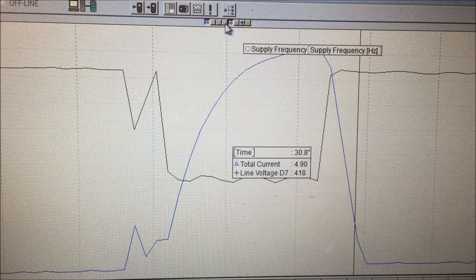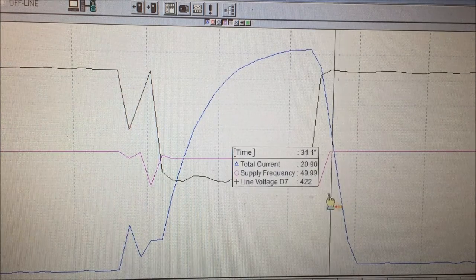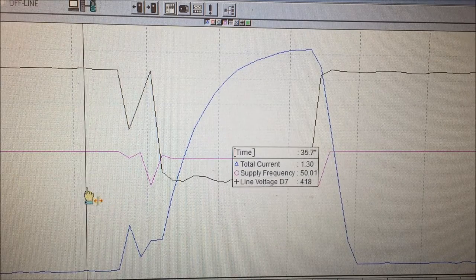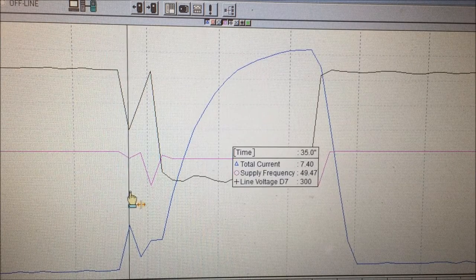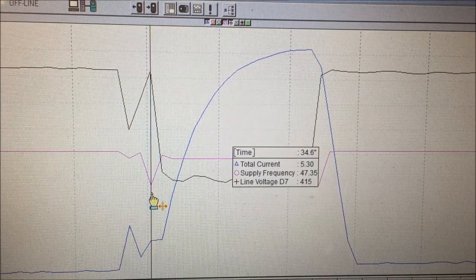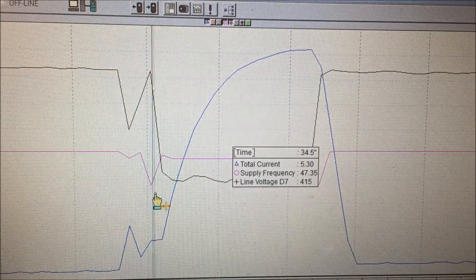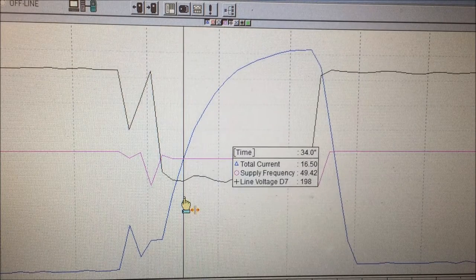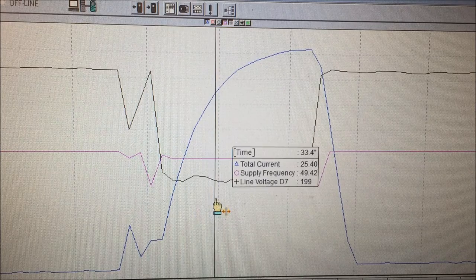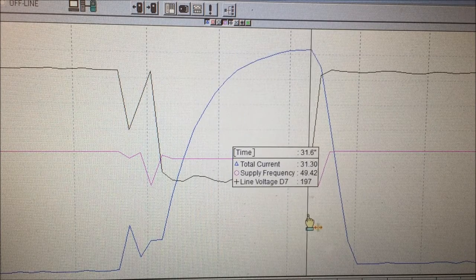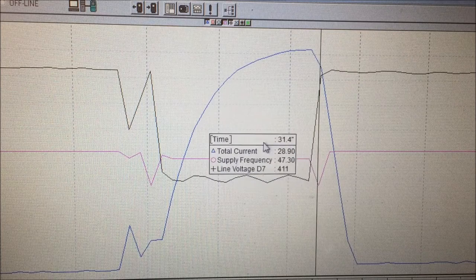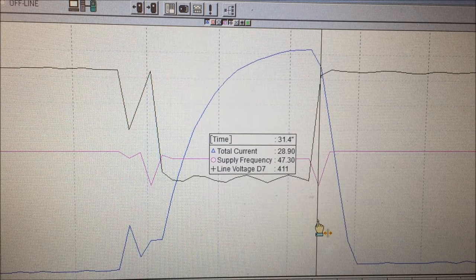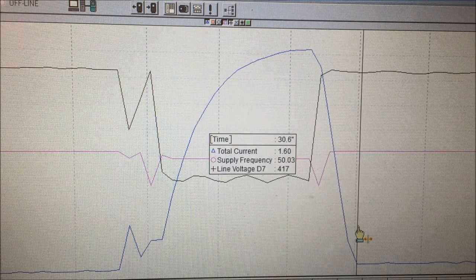What happened with the frequency when this happened? Here we can see the frequency is 50.01 and it doesn't drop here. The moment before the current cutter establishes it comes back into 49.42 hertz, keeps the frequency up during the current cutter operation. There is a small drop here when the transition from current cutter to back to normal operation. Here we got back to normal operation.